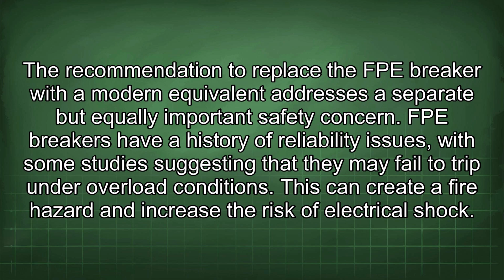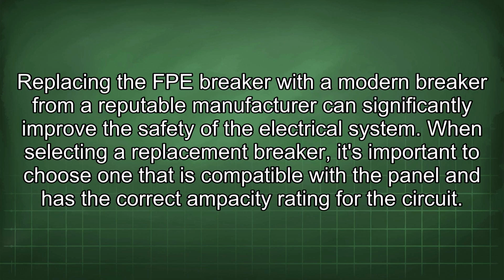The recommendation to replace the FPE breaker with a modern equivalent addresses a separate but equally important safety concern. FPE breakers have a history of reliability issues, with some studies suggesting that they may fail to trip under overload conditions. This can create a fire hazard and increase the risk of electrical shock. Replacing the FPE breaker with a modern breaker from a reputable manufacturer can significantly improve the safety of the electrical system. When selecting a replacement breaker, it's important to choose one that is compatible with the panel and has the correct ampacity rating for the circuit.